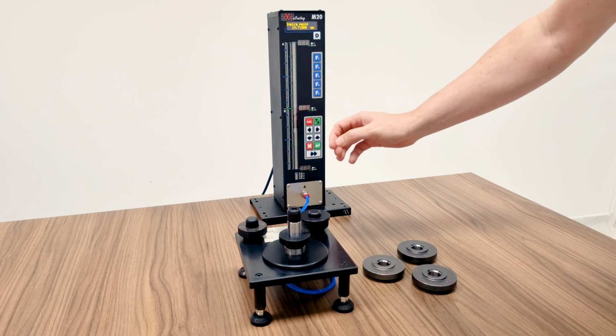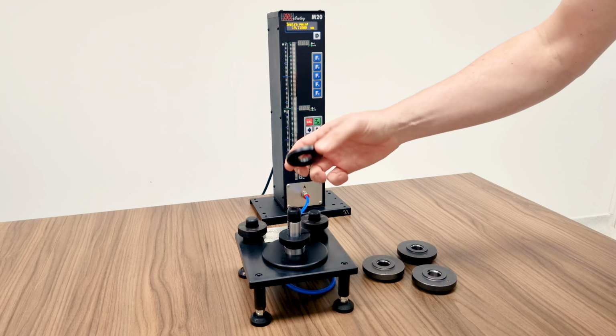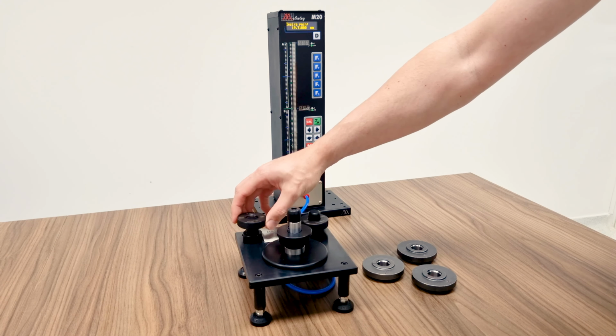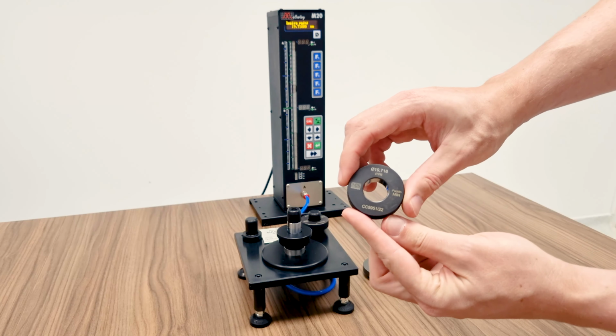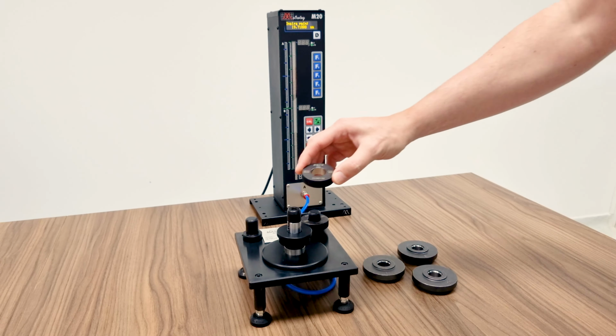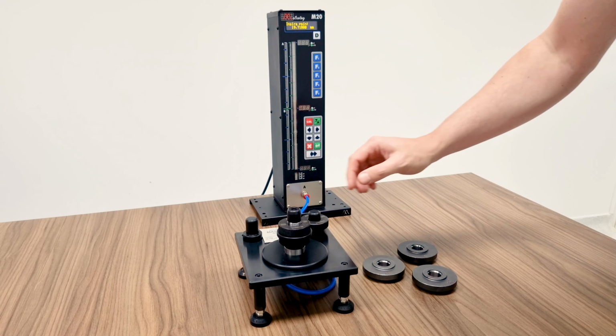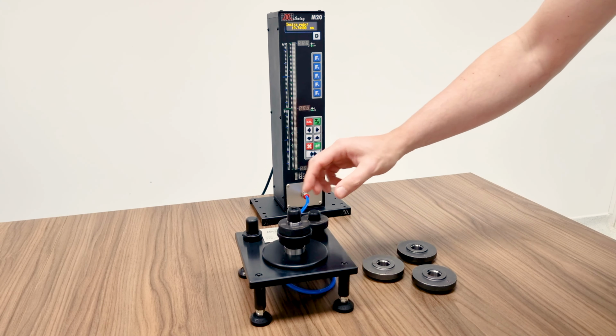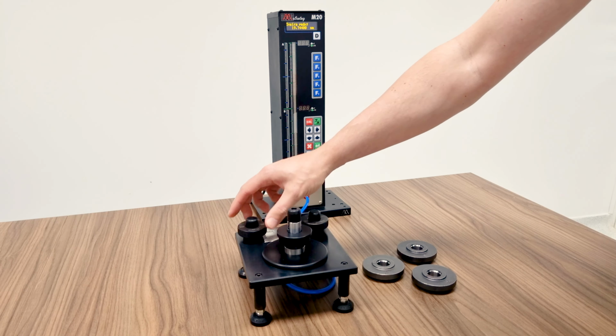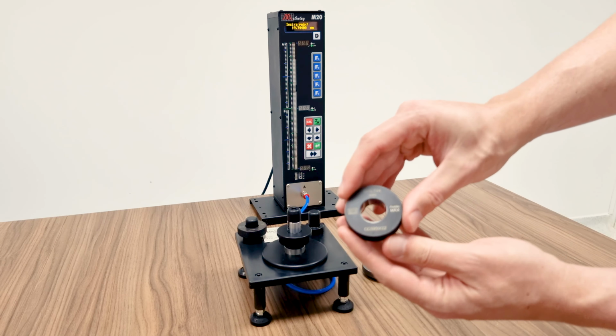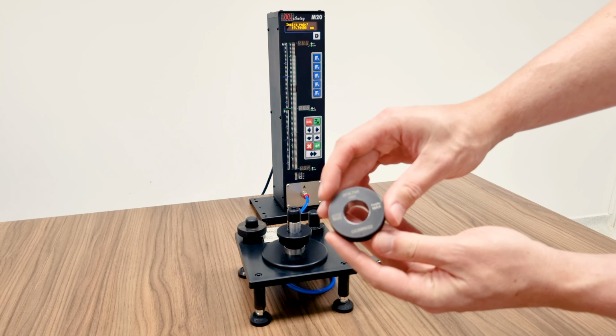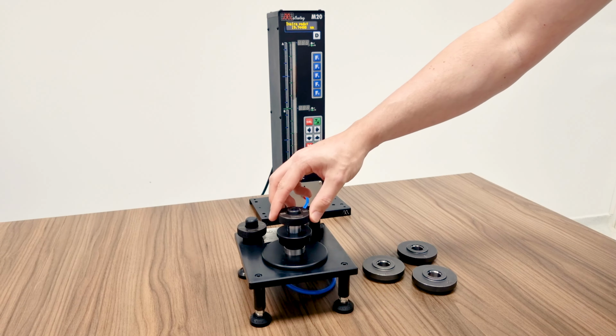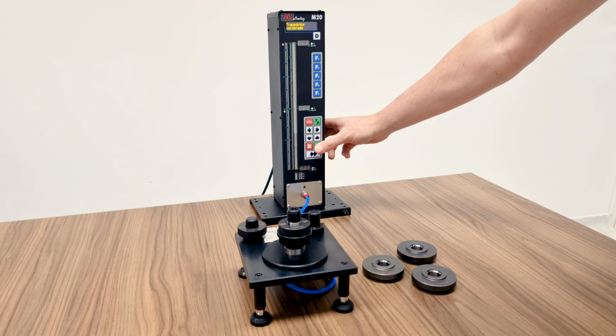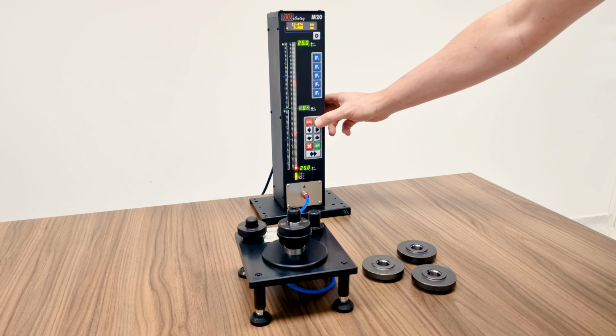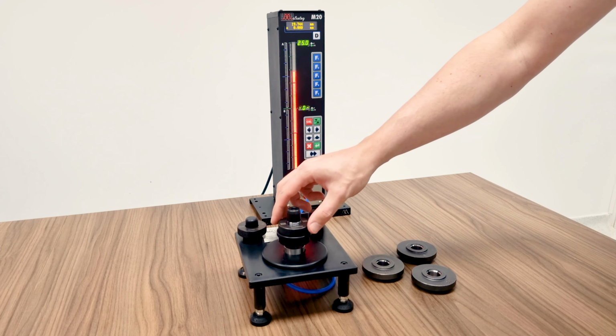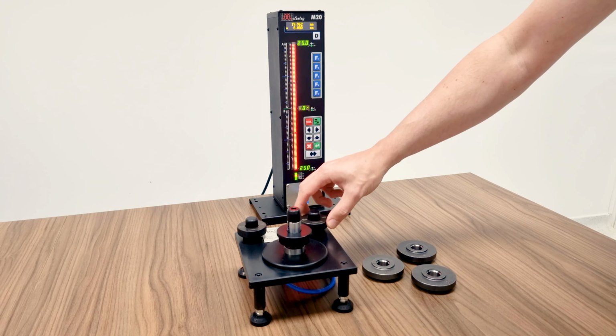The cal key is pressed. The minimum master ring is inserted into the gauge and confirmed. The maximum master ring is then inserted into the gauge and confirmed. Then the zero key is pressed for initial diameter referencing. The gauge is then ready for use.